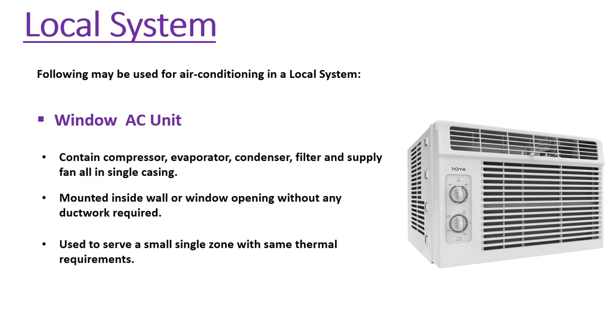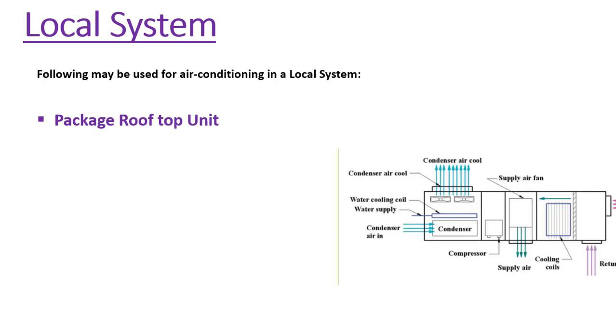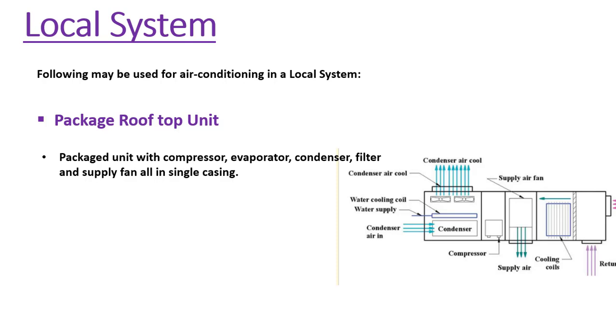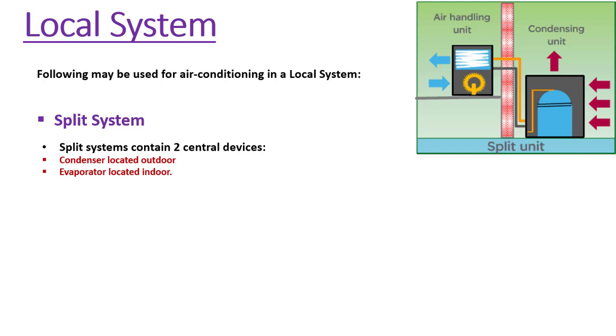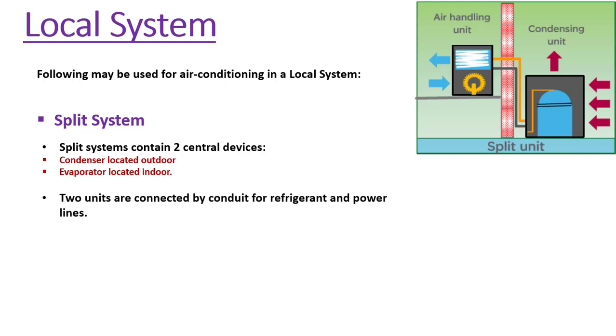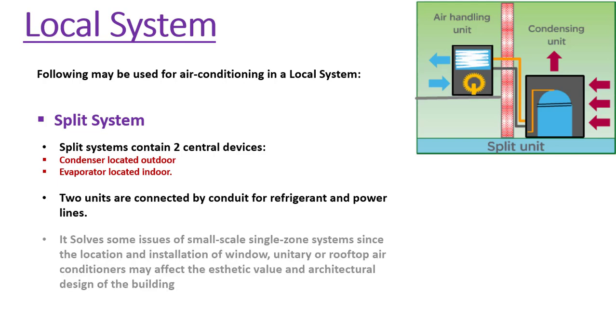Window ACs are mostly used inside homes or small office buildings. A package rooftop unit is a unit with a compressor, evaporator, condenser, filter, and supply fan all in a single casing, but it is mounted on the rooftop and connected to a supply duct to serve a large size zone. A split system uses two separate devices: a condenser located outdoors while the evaporator is located indoors, connected by a conduit for refrigerant and power lines.